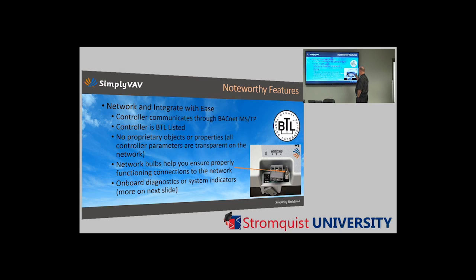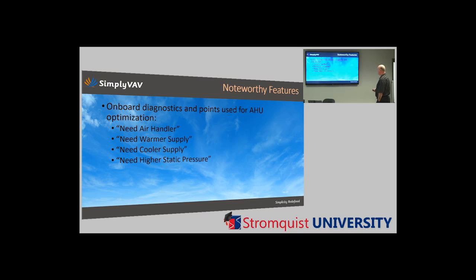You have some network bulbs here that help you to ensure functionality of your onboard communications. In the next slide, we'll talk about what those mean a little bit more. So to give you, for instance, those diagnostics will say things like, hey, I need an air handler out there. Maybe the fan failed or something like that. I have no airflow. Or, hey, I need warmer air, or I need cooler air, depending on what the zones are calling for at the time. Or, hey, I need more static pressure.